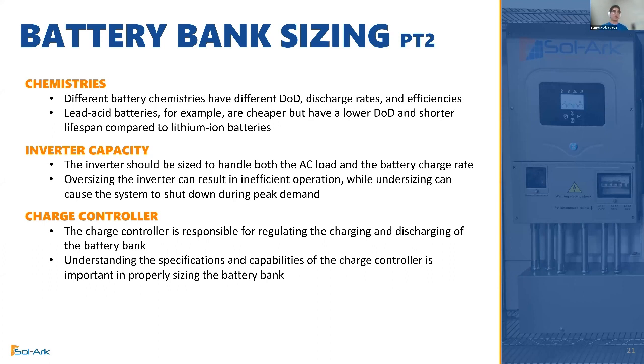Also got to keep in mind the inverter capacity. It should be sized accordingly to handle both the AC loads on the inverter and the battery charge rate that you want the batteries to charge at. For example, oversizing the inverter can result in inefficient operation, while undersizing can cause the system to shut down during, perhaps, peak demand.